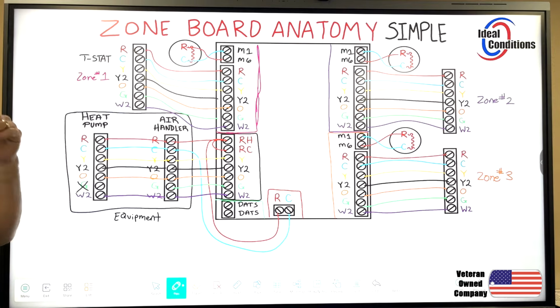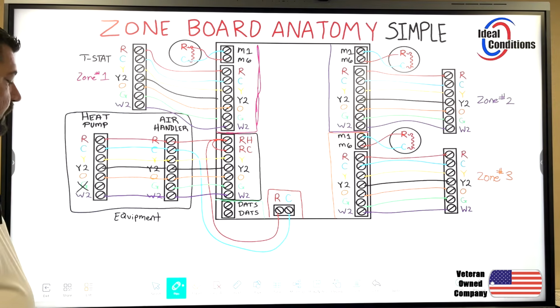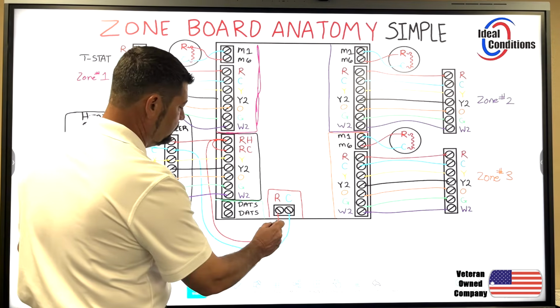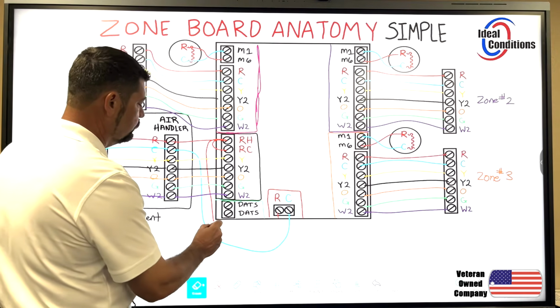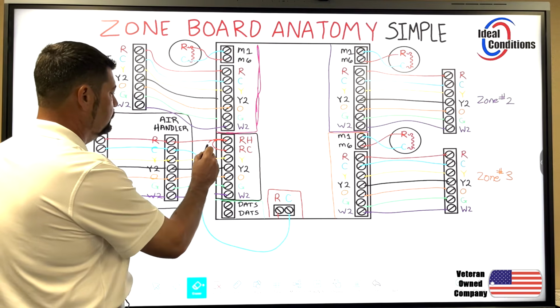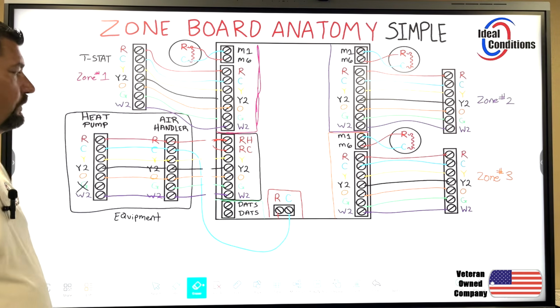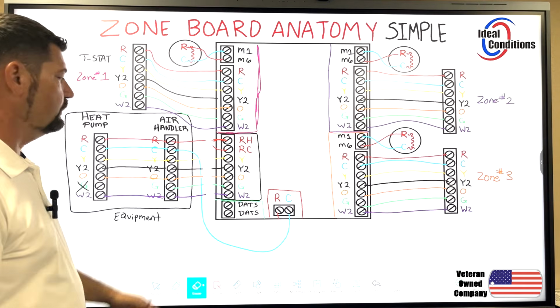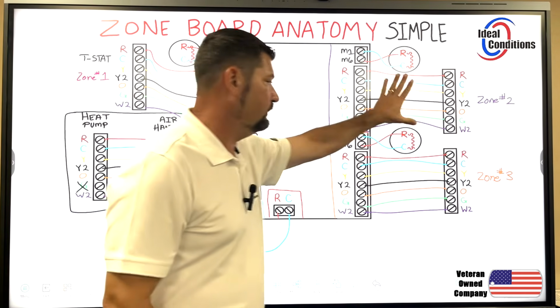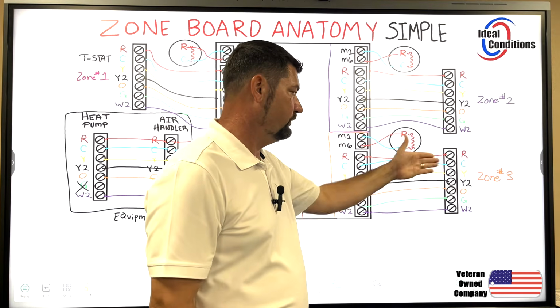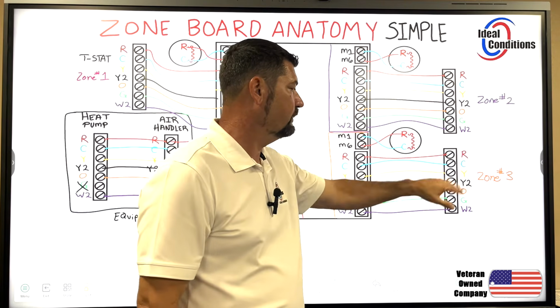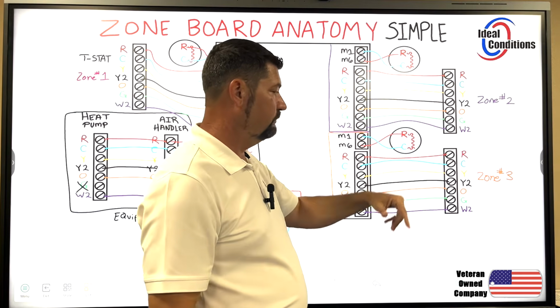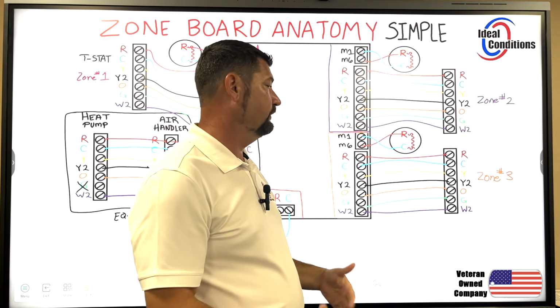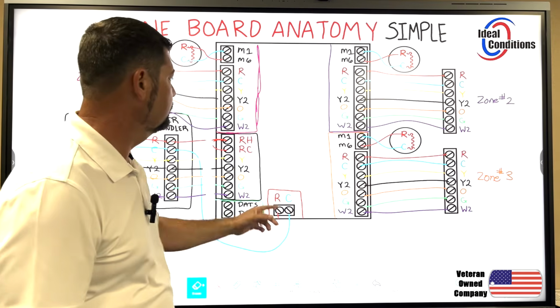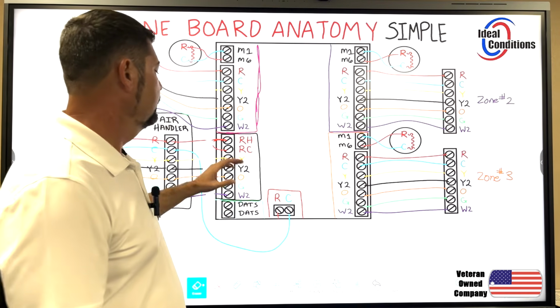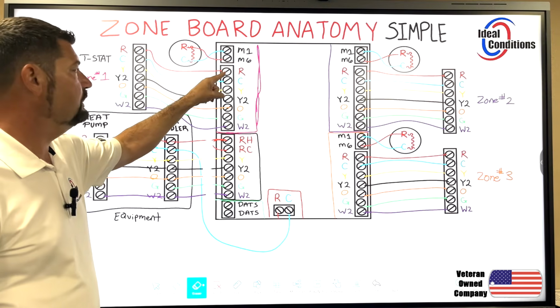One transformer. If you miss this one step here, where you don't take this jumper and run it up to RC and RH, you've got this part wired right, but none of these thermostats say they don't have any batteries, because you don't need them because you're supplying 24 volts alternating current to have the display. So if you have batteries, it'll confuse you because nothing's going to happen. Nothing's going to happen because nothing is energized, and if nothing's energized, then there's no 24 volts here.